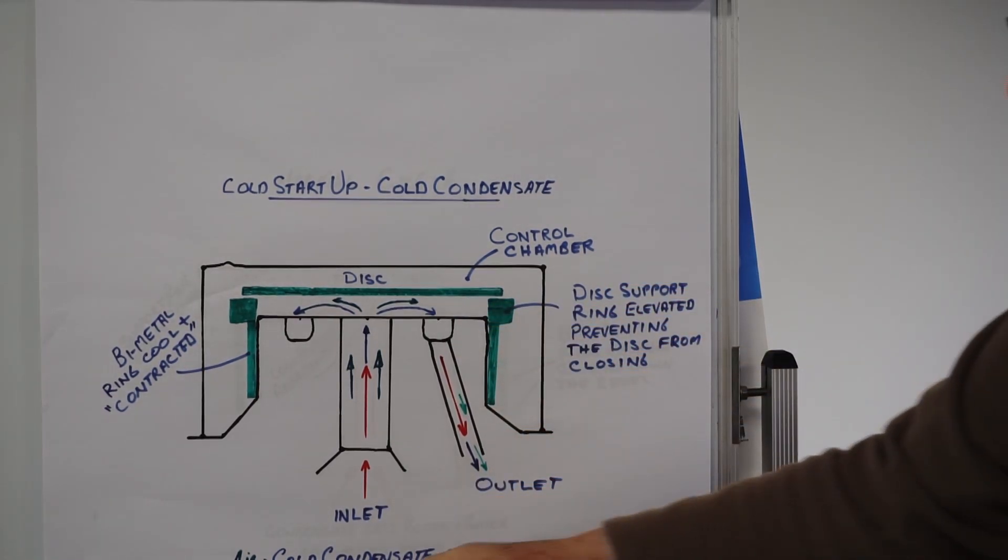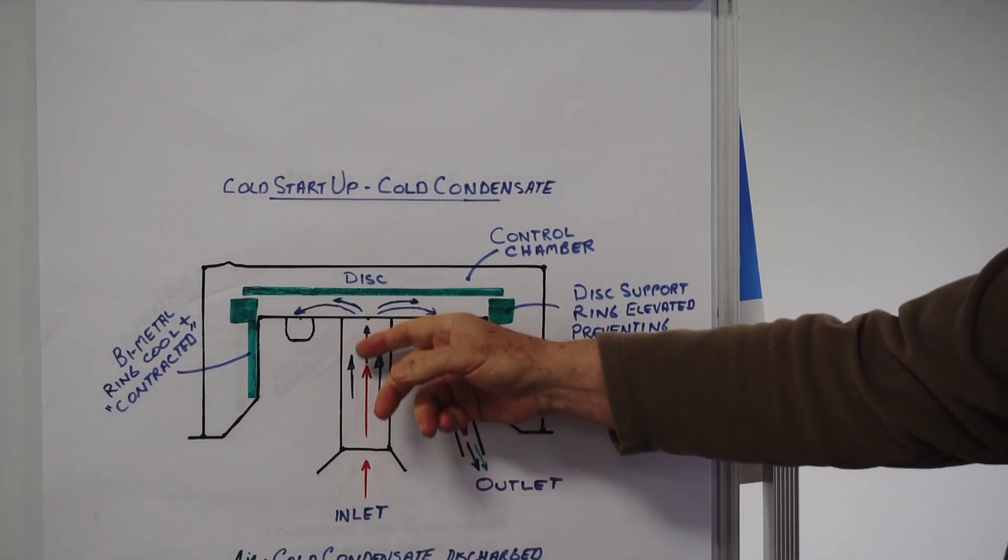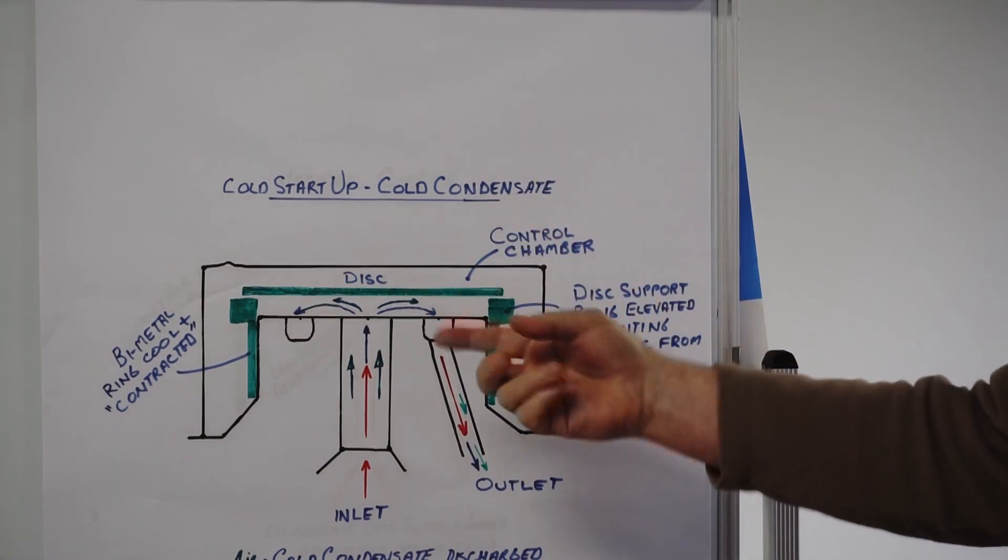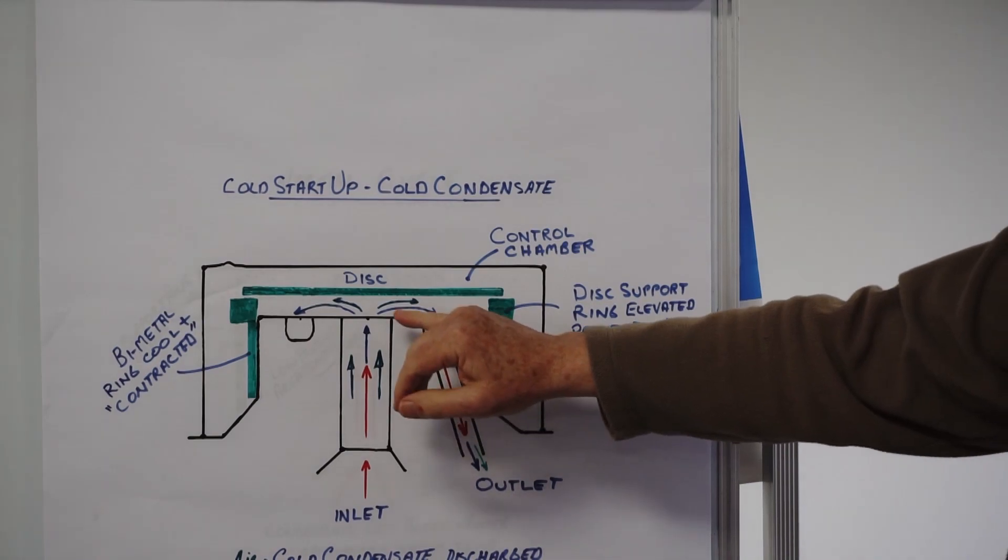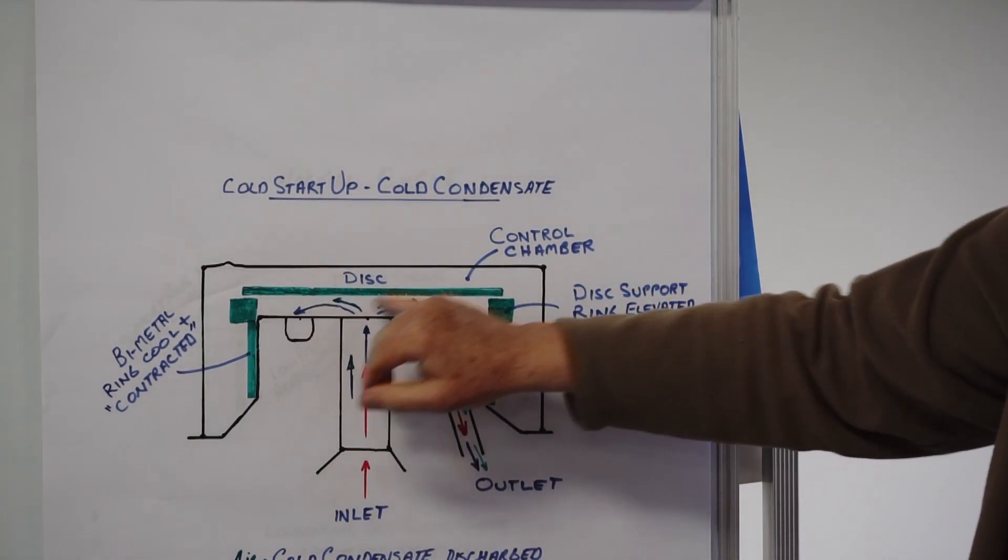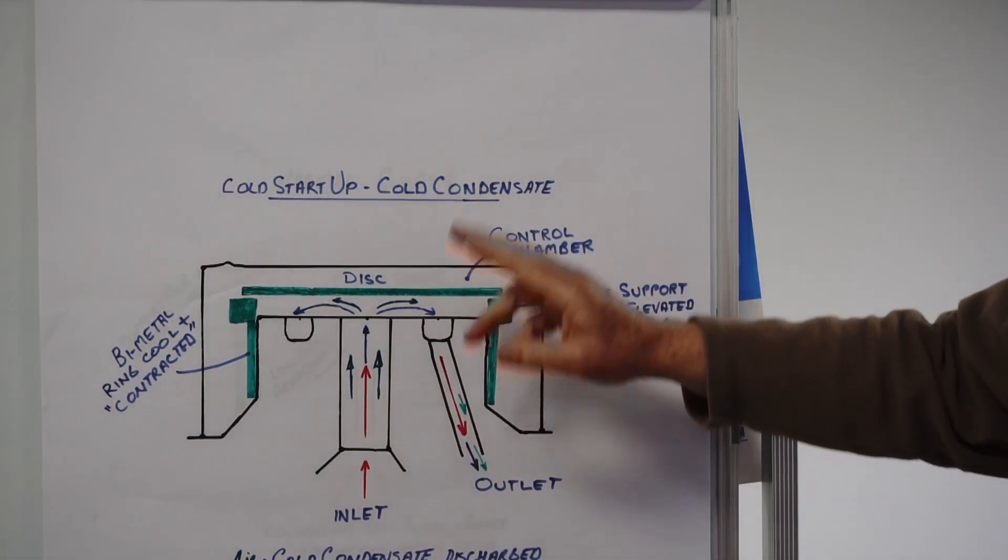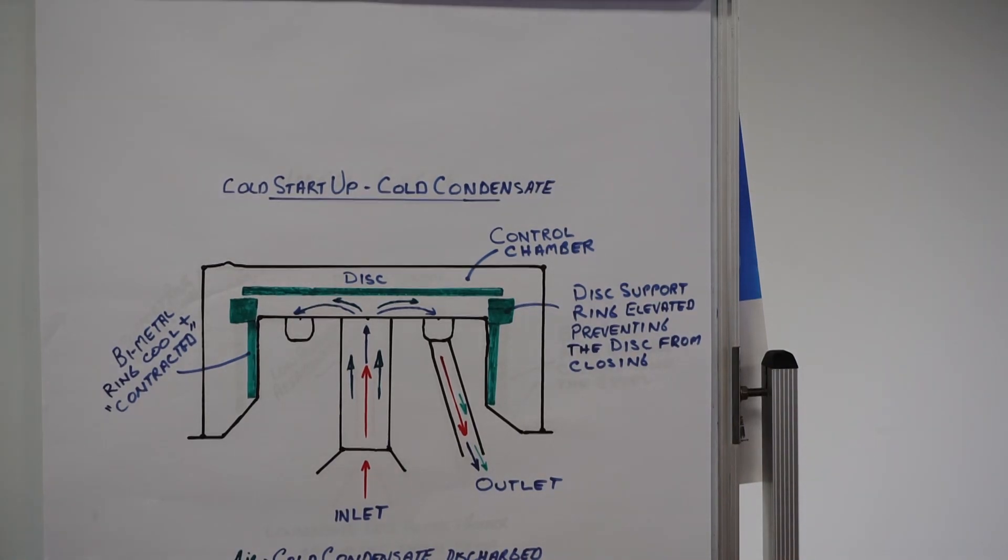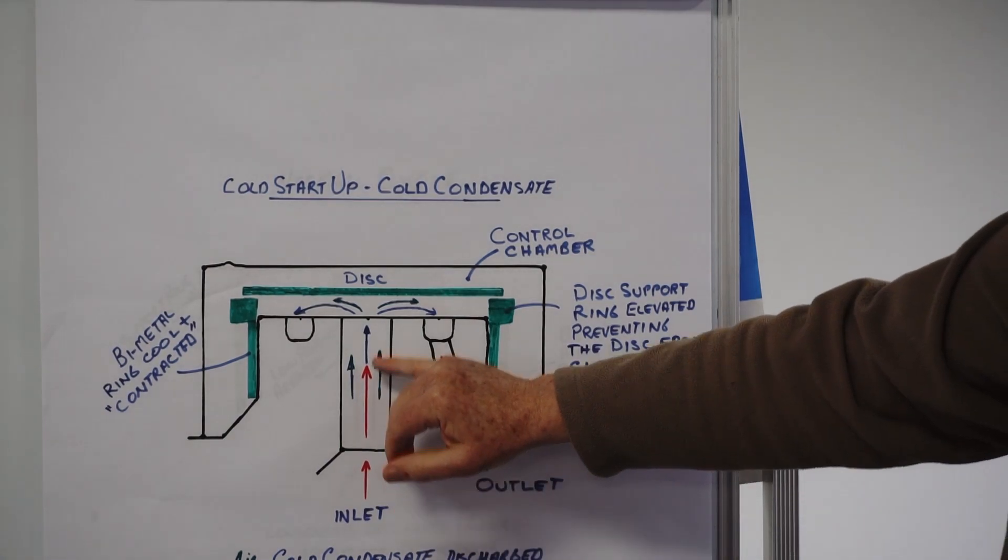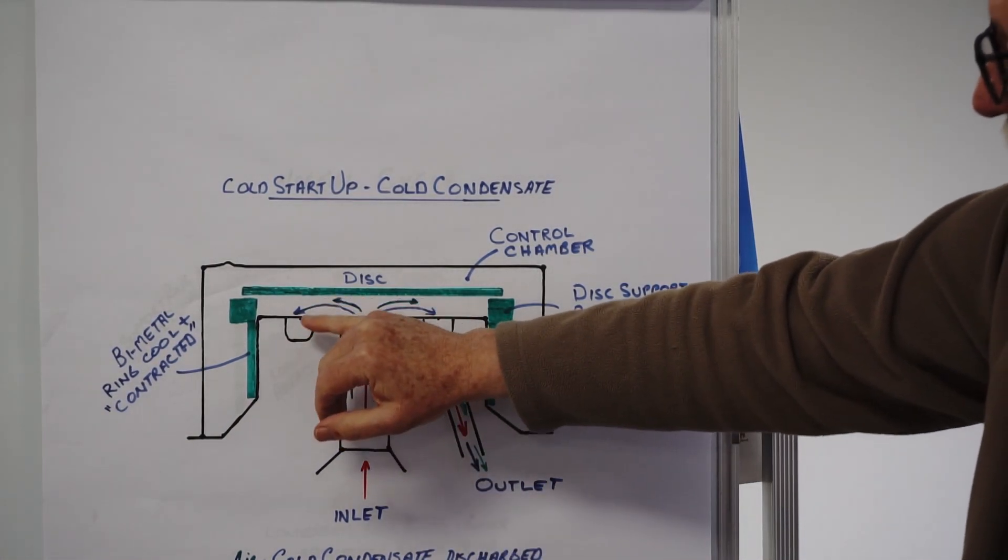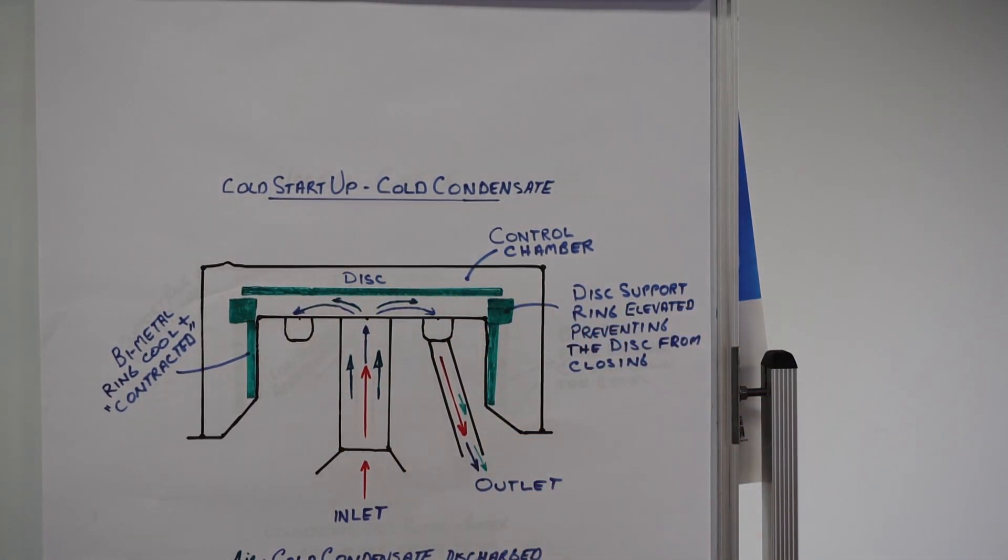When in the cool position, the bimetal ring is contracted very tightly around the body of the trap. When it's tight, it moves up this beveled edge here and lifts this ring up, which then lifts the disc up. So while it's cooling on start-up and you've got cool condensate going in here, all the cool condensate is forced out through the groove and then out through the outlet tube. Any air and other non-condensables will also be forced out through the outlet.